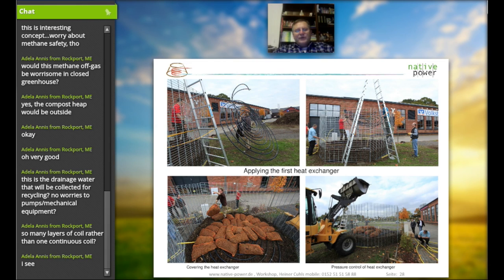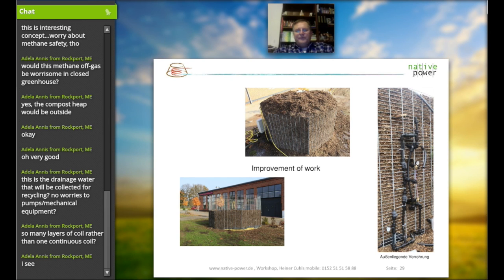Since we had this experience in early work with compost heaps, we decided to put it into separate layers and connect the pipes at the outside — so we have total control of the hydraulic system. Just in case one layer has a leakage, we can isolate and cut that layer out. At the end, if we have two or three working layers from the original four total, we still have adequate heat exchange capacity.